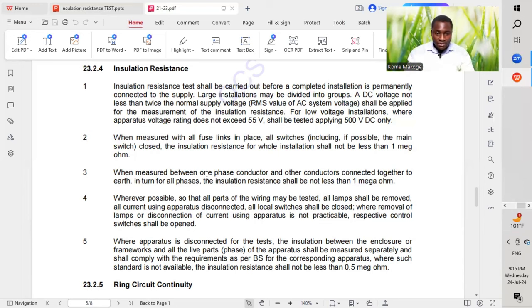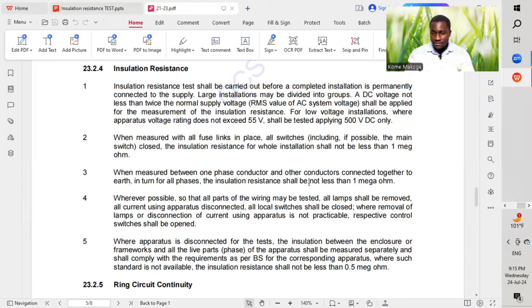When measured between one live conductor and other conductors connected together to earth in turn, for all phases, the insulation resistance shall not be less than 1 megaohm.